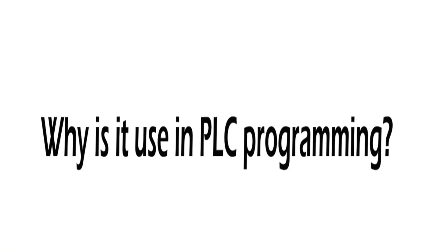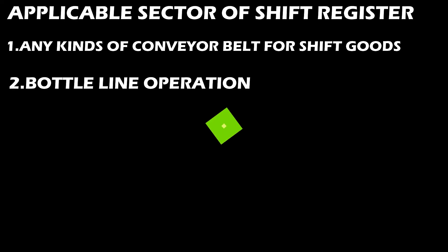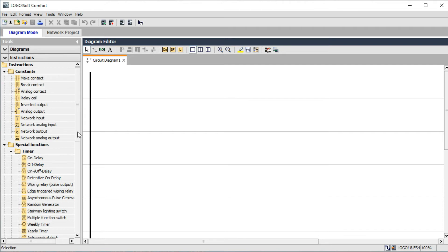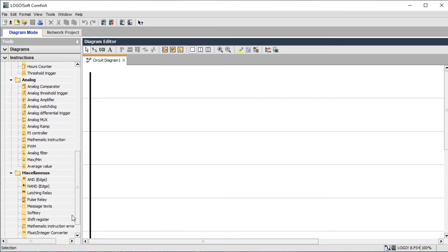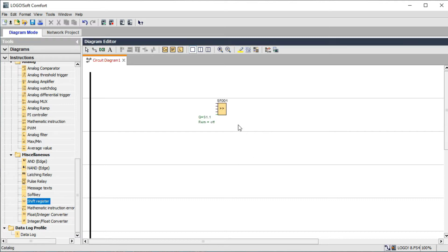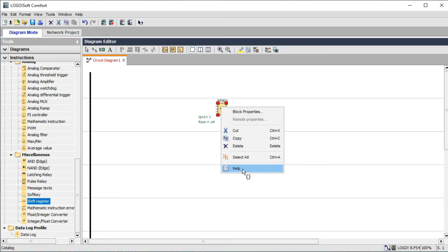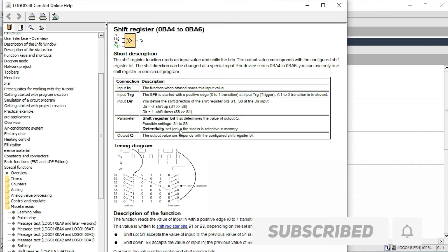Now, why are we using the shift register in PLC programming? We are working on Logo Soft Comfort version 8.1, an updated version with Ethernet systems. Today's topic is shift register. The first parameter we describe is IN — the input function; when started, it reads the value, zero or one, as a digital point. Next is Trigger — this is the pulse trigger; when the digital pulse goes high or low, it triggers. And Direction — this changes your direction: left or right.